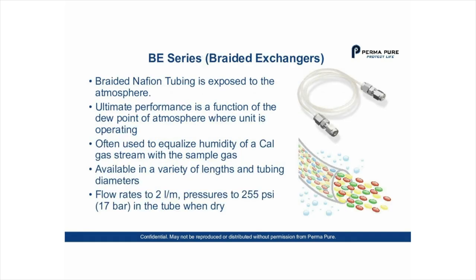Let's look at our products, starting with the BE series — a braided exchanger using braided Nafion tubing exposed to the atmosphere. Ultimate performance is a function of the dew point of the atmosphere where the unit is operating. It is often used to equalize humidity of the calibration gas stream with the sample gas. It's available in a wide range of lengths and tubing diameters, with flow rates up to 2 liters per minute and pressures to 255 psi in the tube when dry. It essentially equates the humidity of the gas stream going through the center of the tube with whatever is outside the tube.